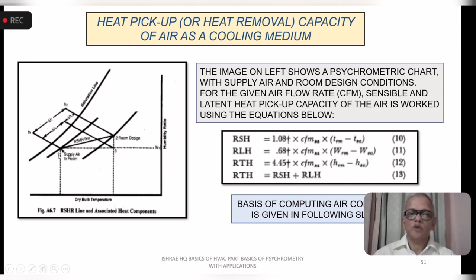Using these parameters, you calculate what will be the resultant room condition, because it has to pick up that given room sensible heat. Depending on that air quantity, you will work out the delta T. You know the temperature of the air being supplied to the space, so you add that delta T to the supply temperature. For that given space sensible load, you will be able to compute the resultant room temperature. Then check whether it is falling within the acceptable tolerance, if design conditions are specified as, say, 73 plus minus 2.